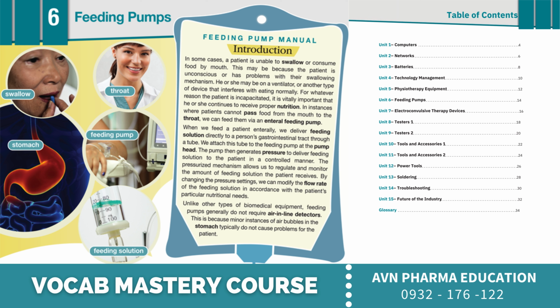The pressurized mechanism allows us to regulate and monitor the amount of feeding solution the patient receives. By changing the pressure settings, we can modify the flow rate of the feeding solution in accordance with the patient's particular nutritional needs. Unlike other types of biomedical equipment, feeding pumps generally do not require air in-line detectors. This is because minor instances of air bubbles in the stomach typically do not cause problems for the patient.